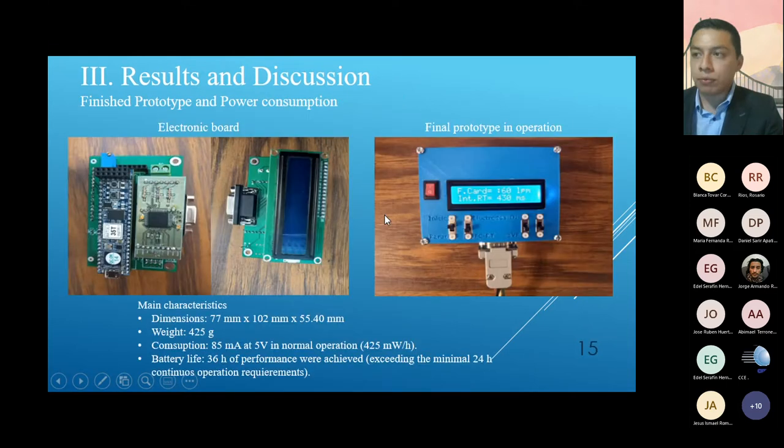The results and discussions: the finished prototype and power consumption. The electronic board was designed to integrate the main elements of the device. The prototype displays in real time the values of the heart rate and the RR interval beat to beat, as we can see.